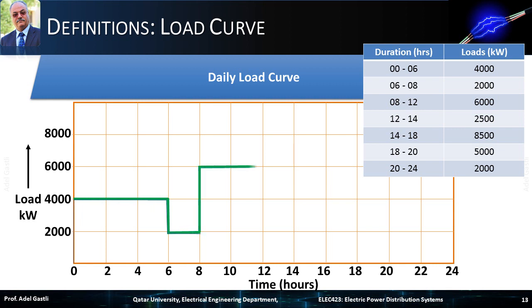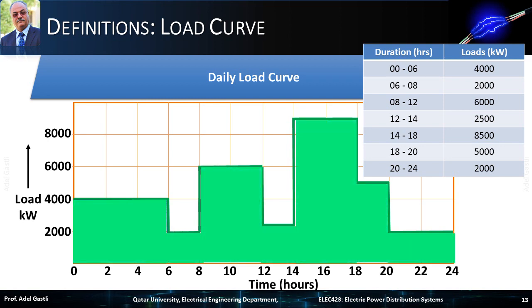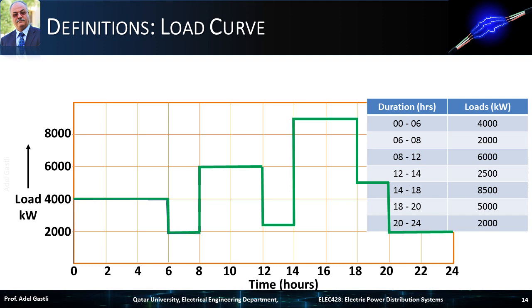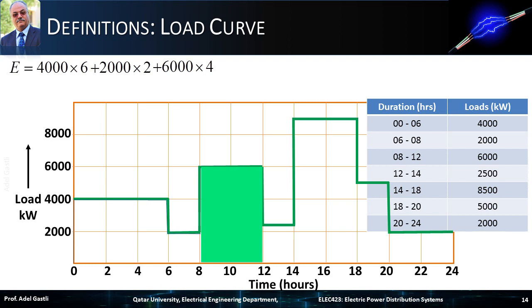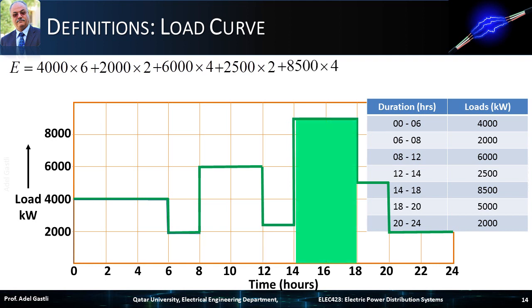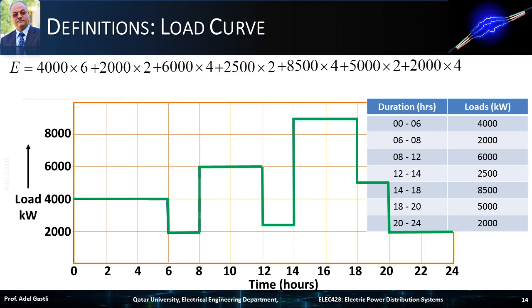Based on the given load data, the load curve is plotted showing the load in kW and its corresponding duration for a whole day, as depicted from this table. The area under the curve represents the energy that has to be generated by the power station in a day to meet the load demands. The total energy generated during 24 hours equals 4,000×6 + 2,000×2 + 6,000×4 + 2,500×2 + 8,500×4 + 5,000×2 + 2,000×4 = 109,000 kilowatt-hours.